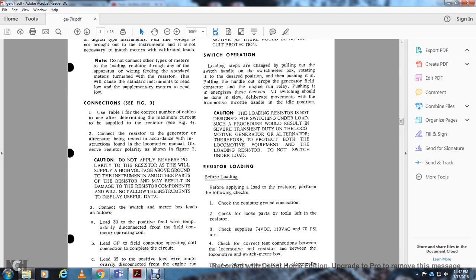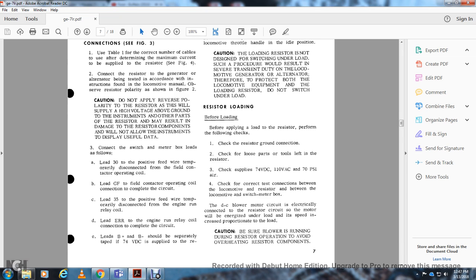Connection, see figure 3. Use table 1 with the correct number of the cable to determine the maximum field current to be supplied to the resistor. See figure 4. Connect the resistor with the generator and alternator being tested in accordance with the instructions found in the locomotive manual. Observe the resistor polarity shown in figure 2. Caution: do not apply reverse polarity to the resistor, as it will supply a high voltage above ground to the instruments and other parts of the resistor and may result in damage to resistor components, and will not allow the instrument to display useful data.